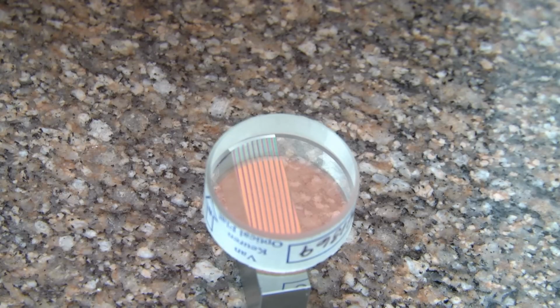The optical flat right now is showing that the face of the gauge block is extremely flat. The interference bands don't cross or bend, they're nice and parallel. Each interference band represents 11 microinches of distance.